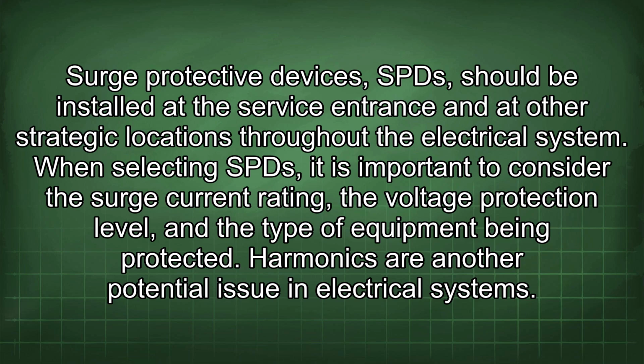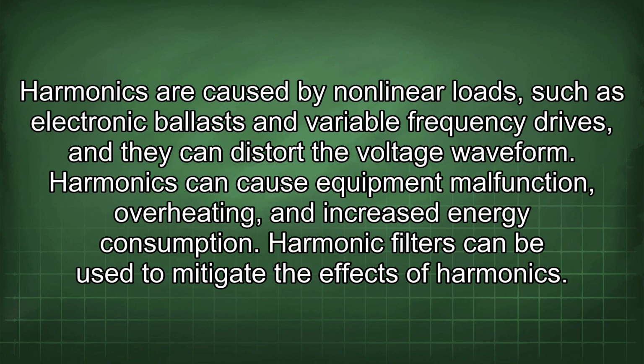Harmonics are another potential issue in electrical systems. Harmonics are caused by nonlinear loads such as electronic ballasts and variable frequency drives, and they can distort the voltage waveform. Harmonics can cause equipment malfunction, overheating, and increased energy consumption. Harmonic filters can be used to mitigate the effects of harmonics.